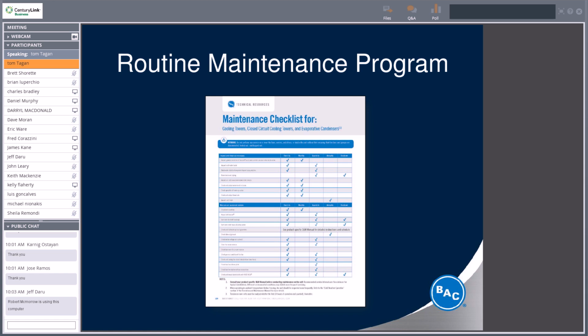Lubricate your fan shaft bearings, lubricate your motor base adjusting screw, check and lubricate the optional gear drive if you're using a gear. The lubrication and the oil of your cooling tower is probably the number one thing on your list. It's probably the number one task that you can perform to extend the life of your bearings, keep your motor operating and your fan operating properly.